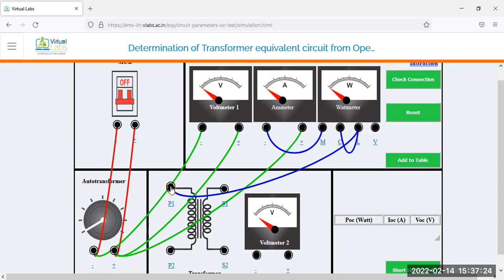Next, measure the no load current with the help of an ammeter. Connect the positive polarity of the ammeter to the positive polarity of the auto transformer, and the negative polarity from the ammeter connects to the M point of the wattmeter. In the circuit diagram, L and C are common, so we short this one. From L, we connect to the LV winding of the transformer - this is the positive polarity and this is the negative polarity. Then from the wattmeter's V point to this point here.